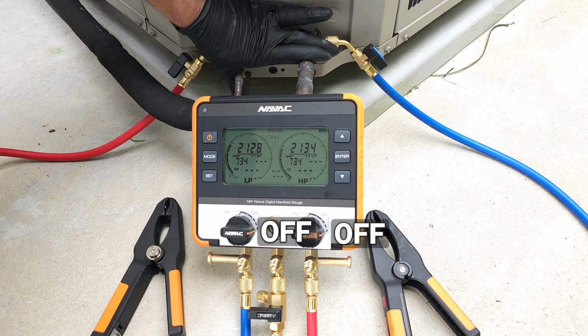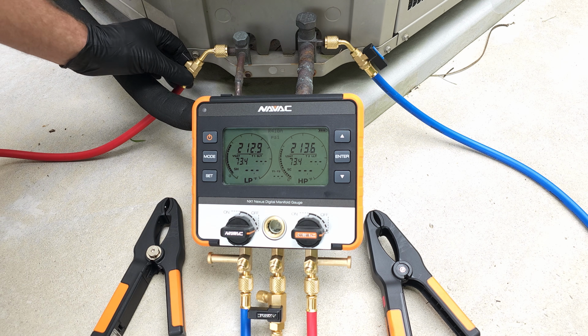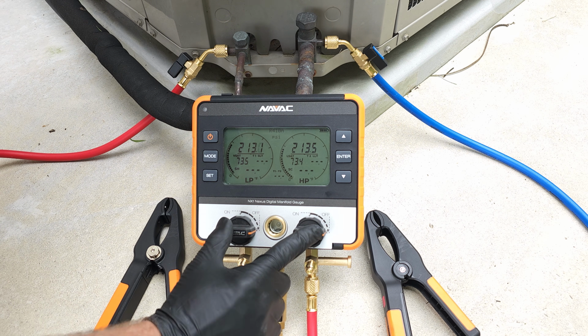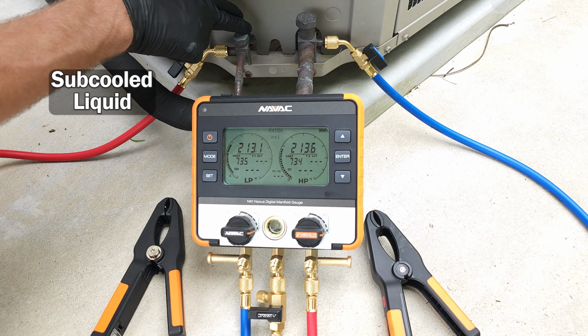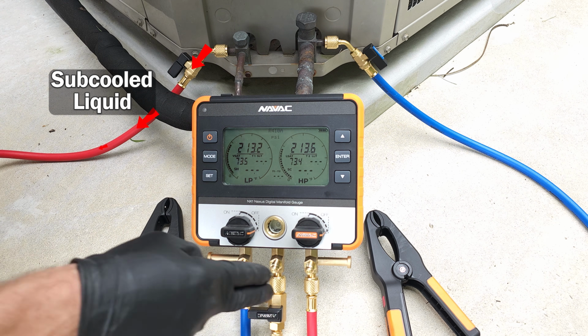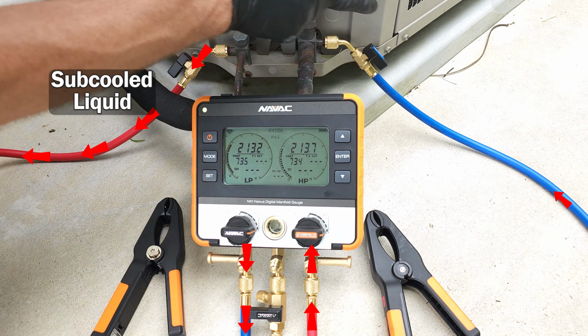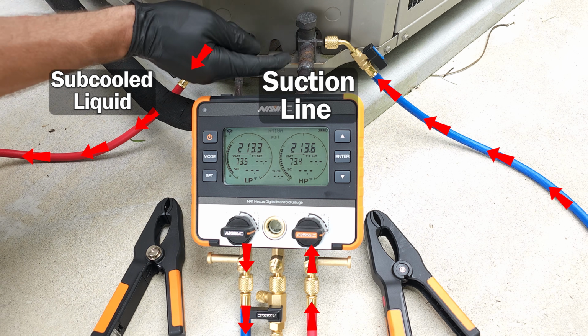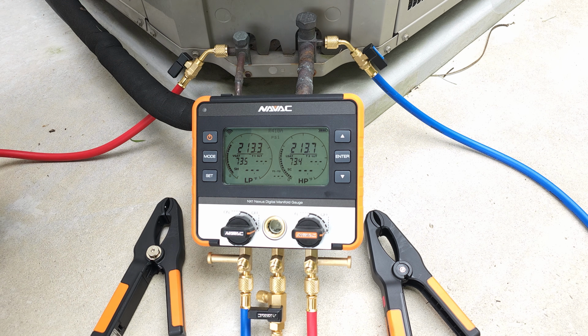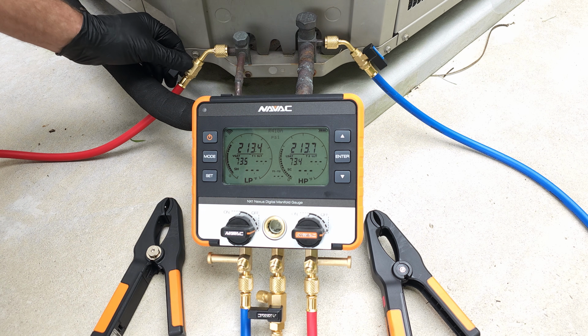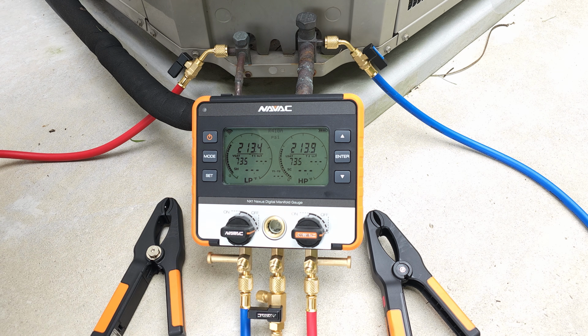If this system was running, after you purge the air out here, you're going to want to turn these off because you don't want to accidentally have subcooled liquid traveling through this hose over to the manifold and back this way into the suction line, because that would end up slugging the compressor. But this system is off right now, and so our manifold's off.